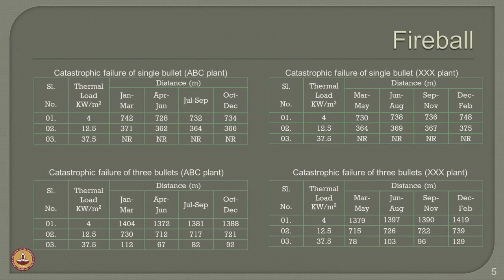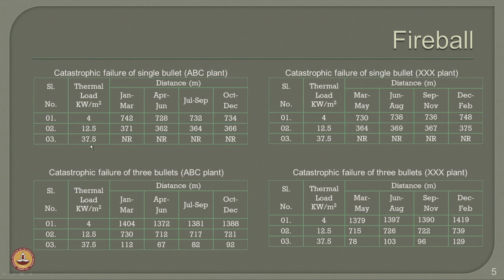The left-hand side shows the consequences of fireball on the ABC plant and the right-hand side table shows the consequences on the XXX plant — catastrophic failure of a single bullet and catastrophic failure of three bullets. For a given thermal radiation intensity varying from 4 to 37.5 kilowatt per square meter, the hazard distances in terms of fireball are evaluated for different cases, different locations, different kinds of failure — single failure or three cascading failures of bullets.